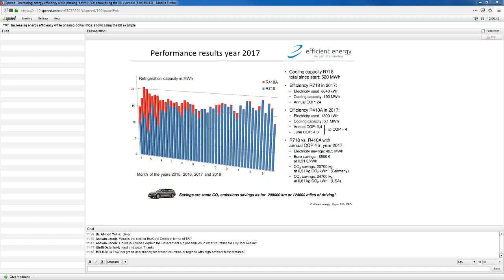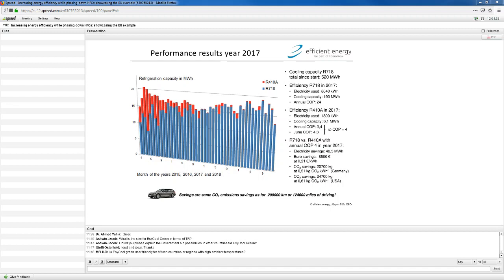COP 24, which means you get 24 kilowatt refrigeration capacity out of one kilowatt electricity used. This is something where some people say to us, well, that's not possible because it's breaking thermodynamic laws. I invite you very much to look at how we do it and how it actually works and why we achieved this large number. But it has been proven over the last three years in this application that it actually worked and also with this efficiency. The R410A system had an annual COP in average of about four, which is a number that people from refrigeration know as, I would just say, as a state-of-the-art average COP over an entire year.